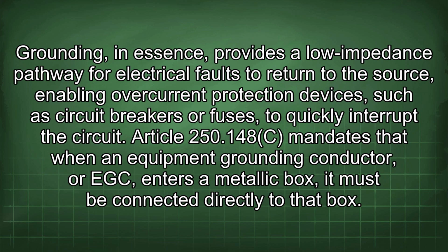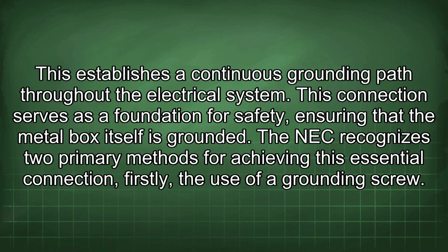Article 250.148c mandates that when an equipment grounding conductor, or EGC, enters a metallic box, it must be connected directly to that box. This establishes a continuous grounding path throughout the electrical system. This connection serves as a foundation for safety, ensuring that the metal box itself is grounded. The NEC recognizes two primary methods for achieving this essential connection.